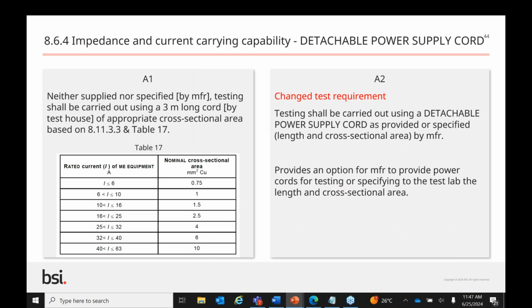Detachable power supply cords weren't always consistently tested by test houses, as they didn't always have a 3-meter cord of appropriate cross-sectional area based on A1 requirements in the table 17. With A2, manufacturers have 2 testing options now. Provide power cords for testing. And in reality that would mean you provide each version if you have different power cords for various countries, lengths, currents, cross-sectional areas, etc. We recommend manufacturers test each power cord that is being shipped, go through this production line test so you can confirm the power cords are safe to ship. That's we as my consulting firm. The second option is manufacturers specifying the length and cross-sectional area to the test house. Next slide, please.